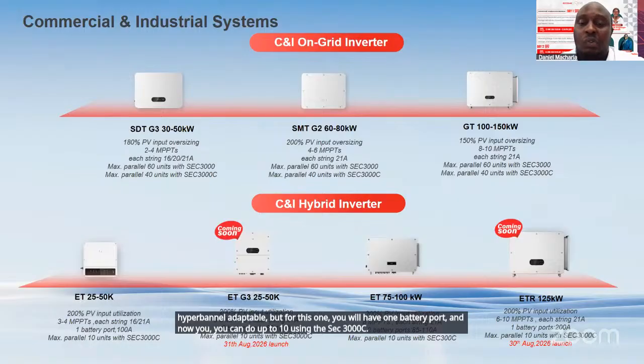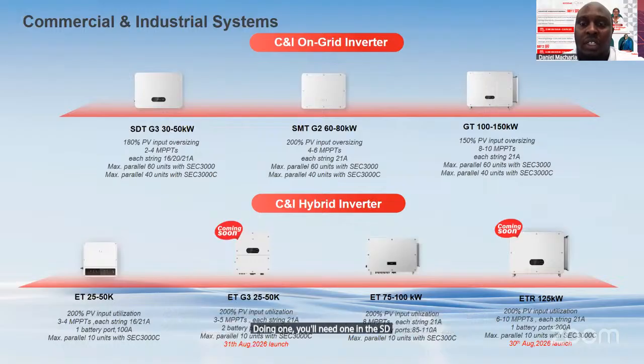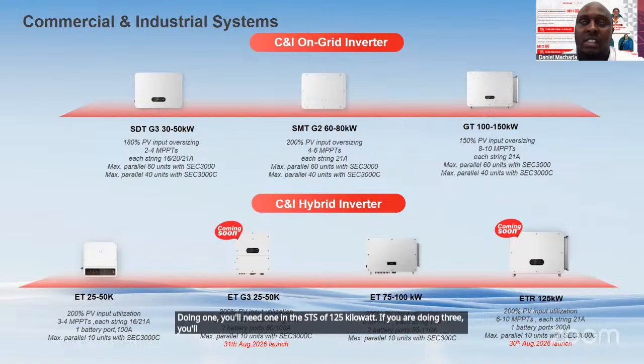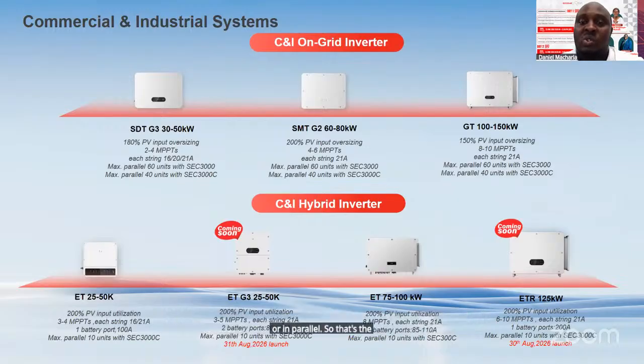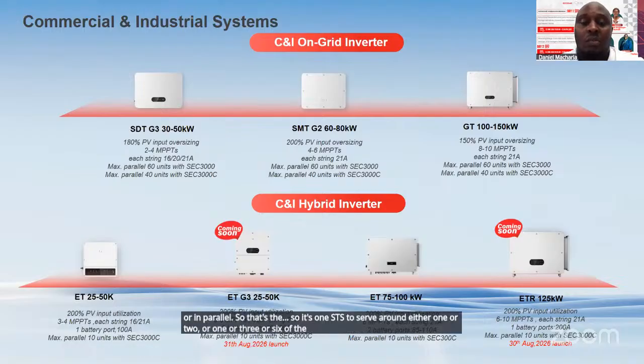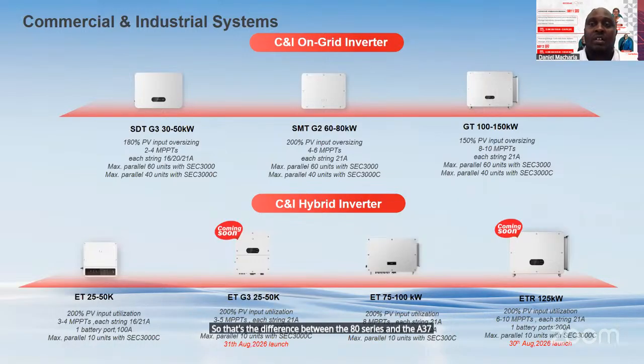The ET75 to 100 utilizes an external STS, but the good thing with this one is that you don't need an independent STS for each inverter. So you have 3 categories. If you are doing one, you'll need one STS of 125 kilowatt. If you are doing 3, you'll need one STS of 375 kilowatt. If you are doing up to 6, you'll need an STS of 750 kilowatt. So it's one STS to serve either 1, 3 or 6 of the ET75 to 100 kilowatt in parallel. So that's the difference between the ET series and the ET75 to 100 kilowatt.